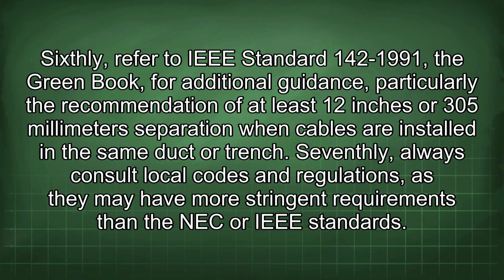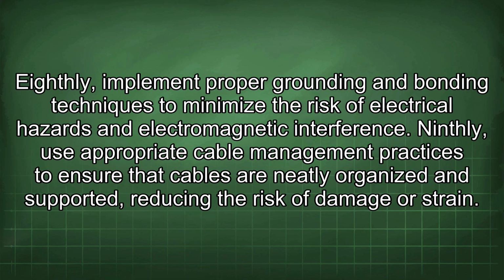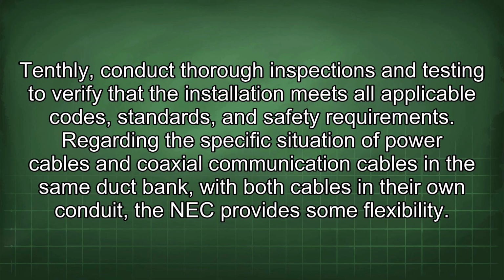Sixthly, refer to IEEE Standard 142-1991, the Green Book, for additional guidance, particularly the recommendation of at least 12 inches or 305 mm separation when cables are installed in the same duct or trench. Seventhly, always consult local codes and regulations, as they may have more stringent requirements than the NEC or IEEE standards. Eighthly, implement proper grounding and bonding techniques to minimize the risk of electrical hazards and electromagnetic interference. Ninthly, use appropriate cable management practices to ensure that cables are neatly organized and supported, reducing the risk of damage or strain. Tenthly, conduct thorough inspections and testing to verify that the installation meets all applicable codes, standards, and safety requirements.